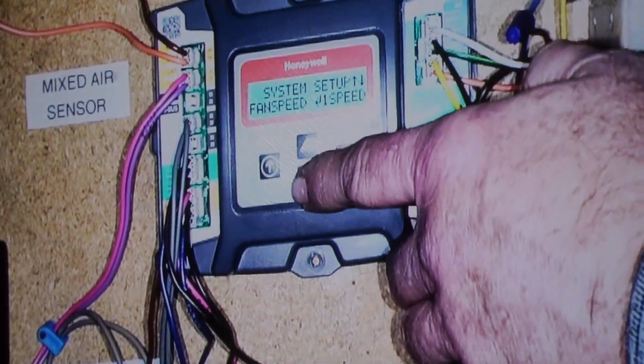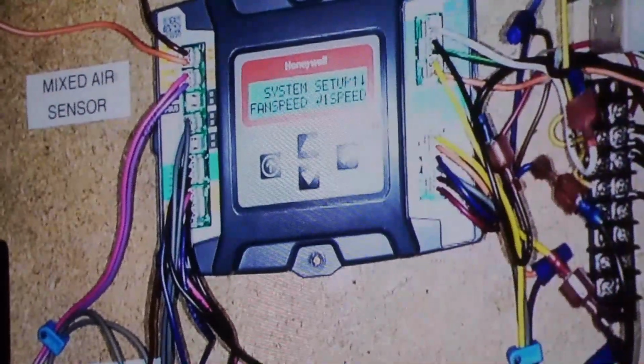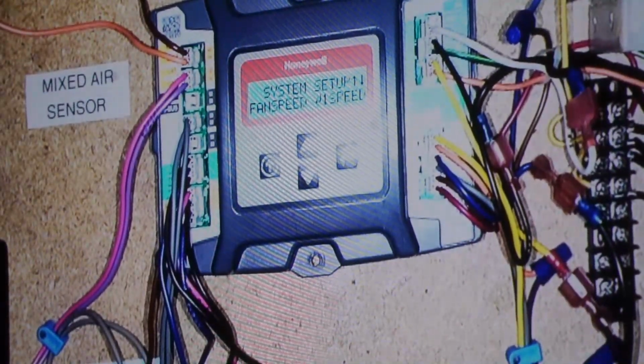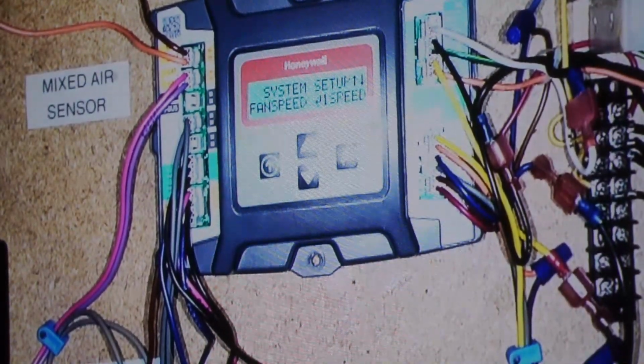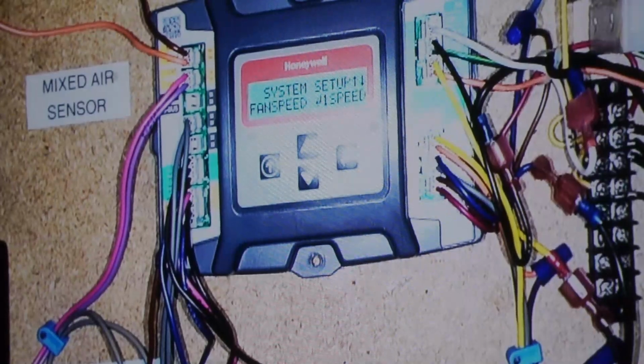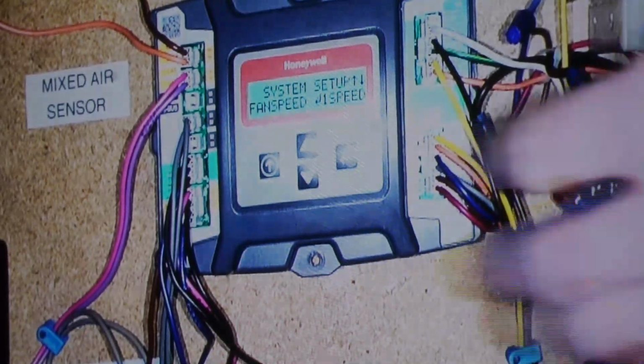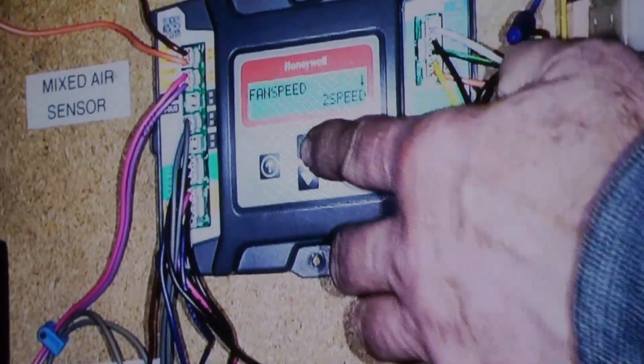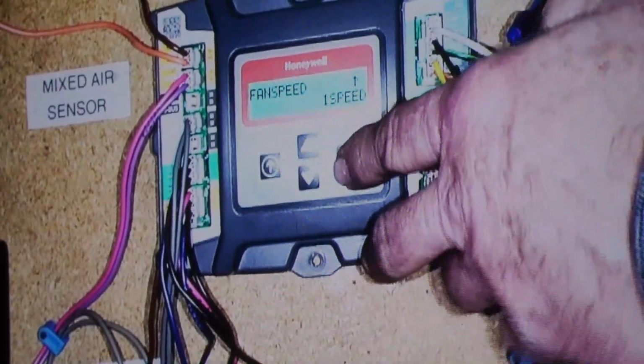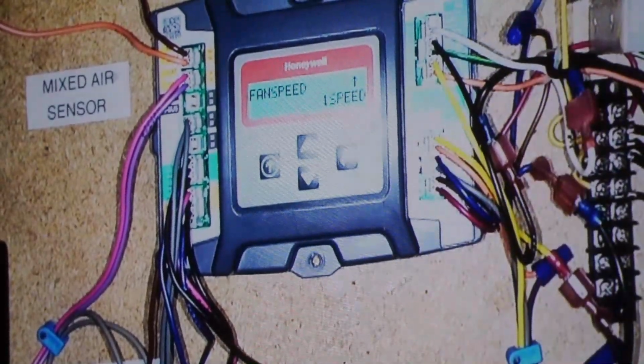Fan speed, this one's a single speed. The default on this is 2-speed. So if you've got a 7.5 ton and below with a single speed fan, change it right here. Otherwise you're going to get 2 different set points.